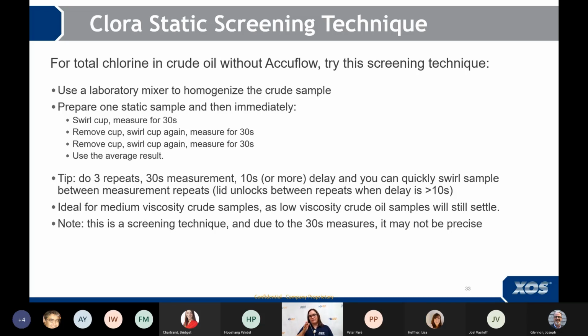And when you set it for 15 seconds there, the lid will actually unlock between the measurements. So what you do is you put your sample in, you swirl it, you put it in, you measure it for 30 seconds. And when that repeat delay is 10 seconds, the lid unlocks. So you open up the lid, you reach in real quick, go like this and put it back and measure it. And you do this repeatedly. And so that way you can look at your printout and you have all the statistics computed rather than running 3 individual measurements and then hand averaging them. Note that this technique is ideal for the medium viscosity type crude samples. If it's a very low viscosity, it's still going to settle during that 30-second measurement time.